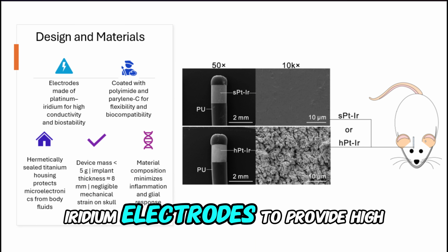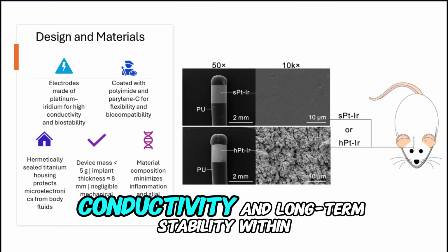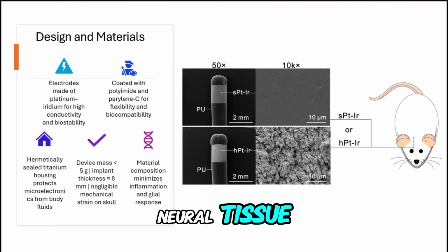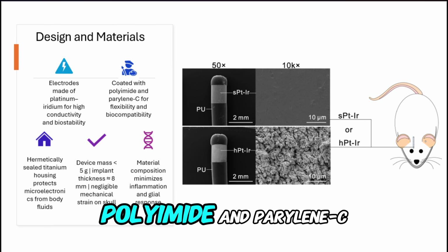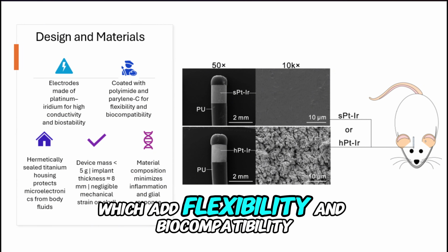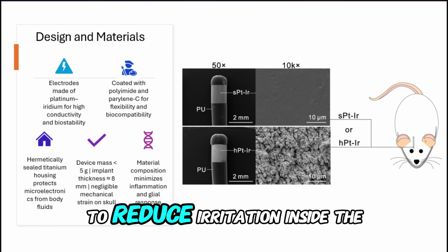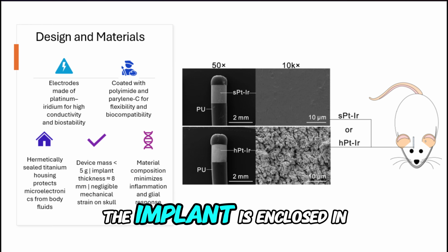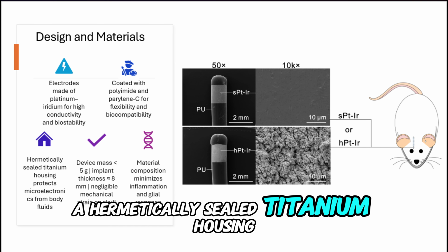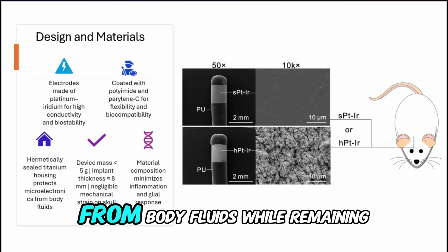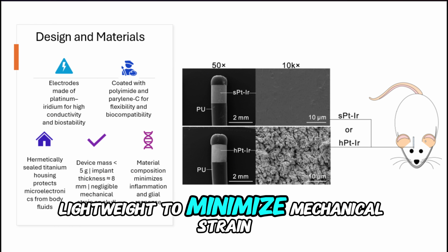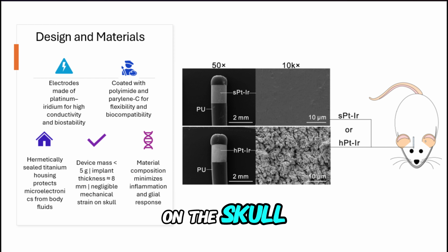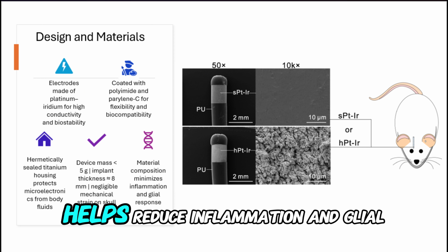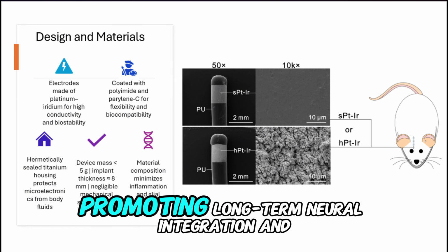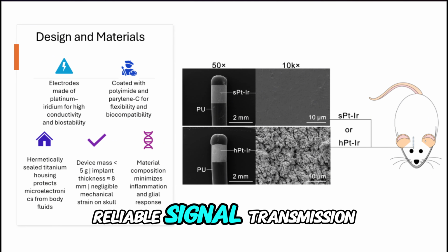The neural implant uses platinum iridium electrodes to provide high electrical conductivity and long-term stability within neural tissue. Each electrode is coated with polyimide and parylene C, which add flexibility and biocompatibility to reduce irritation inside the brain. The implant is enclosed in a hermetically sealed titanium housing that protects the microelectronics from body fluids while remaining lightweight to minimize mechanical strain on the skull. The carefully engineered material composition helps reduce inflammation and glial scarring, promoting long-term neural integration and reliable signal transmission.